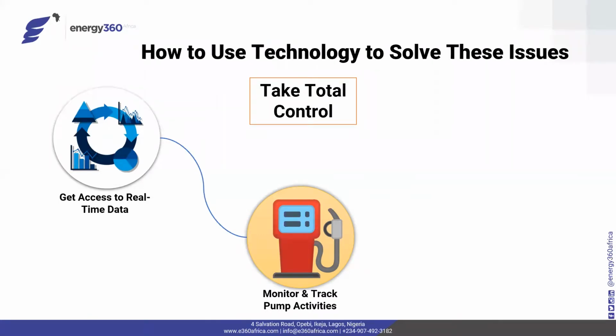Technology can help by monitoring your pump activities, giving you full prescriptive data on pump tolerance, nozzle flow rate, and pump behavior. Your nozzle flow rate is important because you don't want customers queuing for too long if your nozzle isn't dispensing 35 liters within a minute. The moment your pump starts dispensing 20 or even 10 liters a minute, that's a cause for concern, either the pipelines are dirty or something's wrong with the pump and it needs to be changed. Otherwise, you'll have disgruntled customers who can't wait, especially in this fast-paced environment.